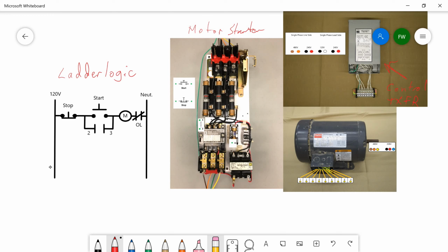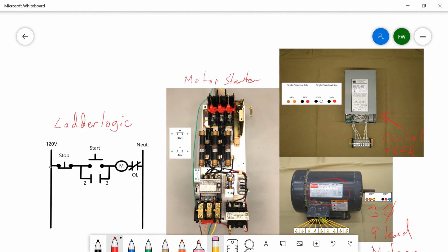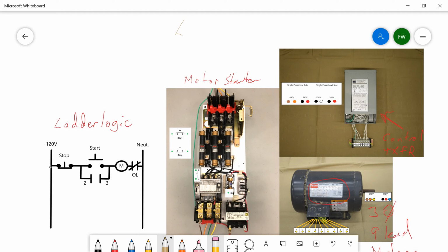And then down here, this is our 3-phase 9-lead motor. And we're going to hook this up for high voltage, so we're going to be using brown, orange, yellow. So L1, we'll have it as brown, and basically we're going to take that in to the top. We're going to have L2 as orange, take that as our B phase, and L3 is going to be yellow.